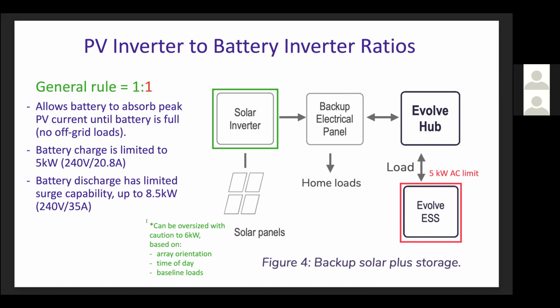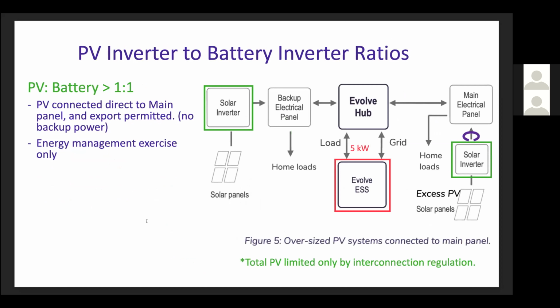With caution, I hesitate to put this on here, but I did put it on here. The solar that's attached to the backup loads panel, with some caution, can be oversized on the nameplate rating to about 6 kW or 5,800 watts based on the array orientation, time of day, and baseline load. Again, the limitation is the excess PV generation. So if there's ever a chance of there being no backup loads, or maybe 100 watts of backup loads on a high efficiency load panel, and you've got more than 5,200 watts of generation, then that excess PV is going to be 5 kW or greater. You will trip the battery offline and none of those loads will be served. So again, with caution, a little bit of room to fudge that a little bit.